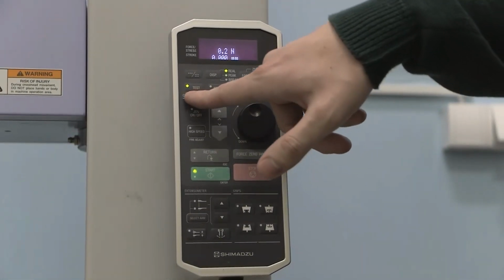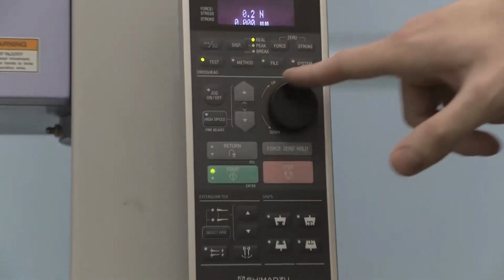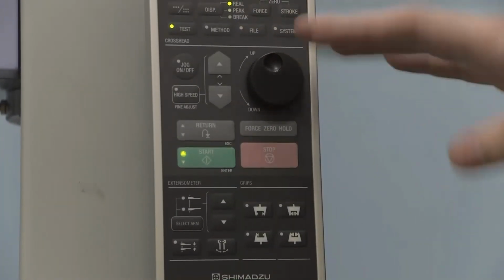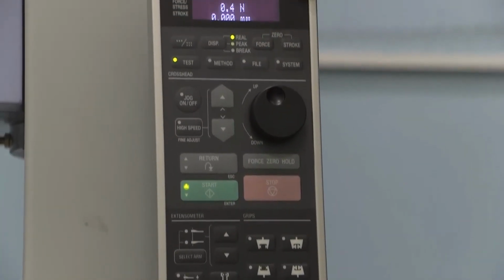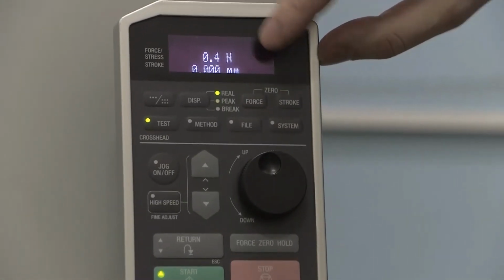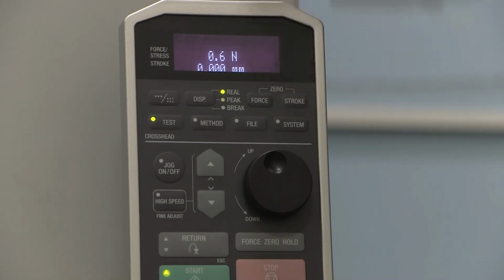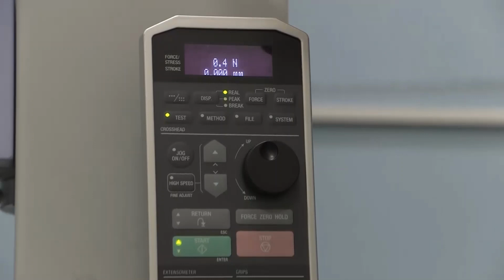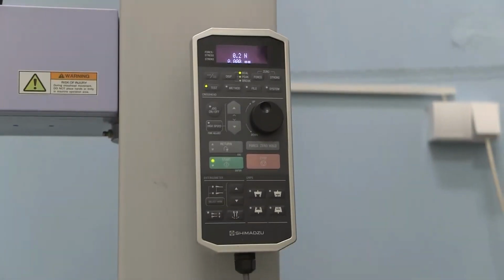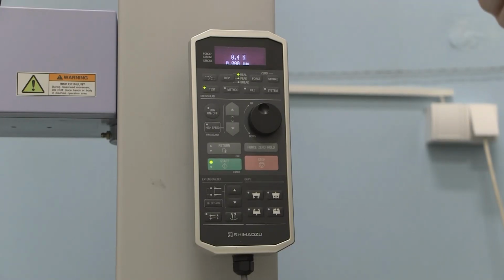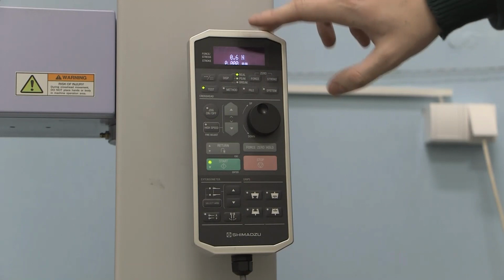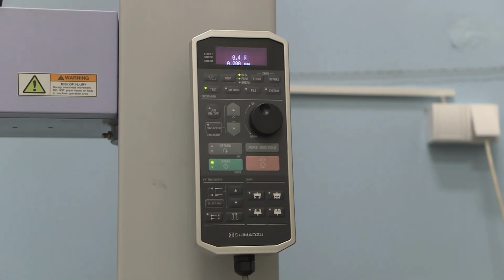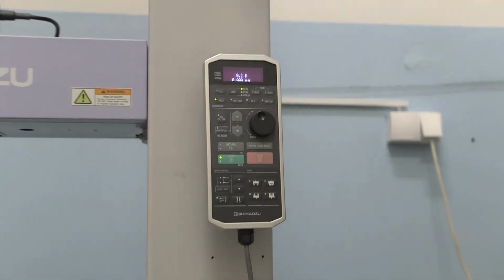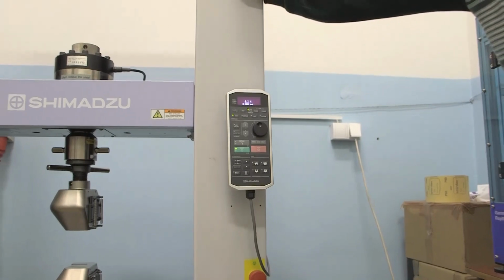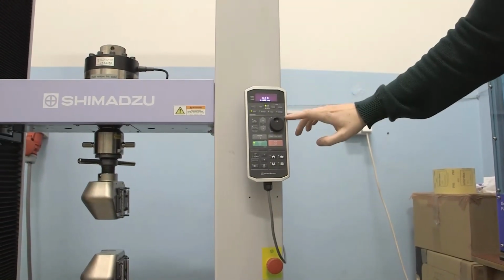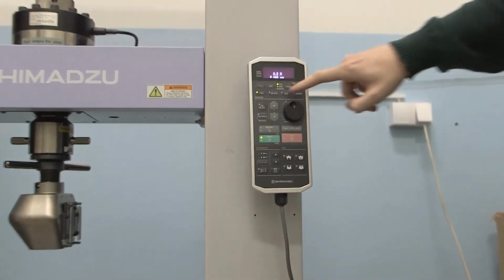So we have clicked the test button, so we are about ready to perform testing. On the panel you see the calculated force and displacement on this machine. First, we apply force, and the specimen has some pathway. It displaces in millimeters. And the stress and strain values which we need for the testing are calculated from the dimensions of the specimen. This is about the upper commands on this panel.